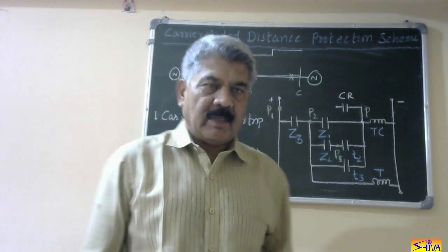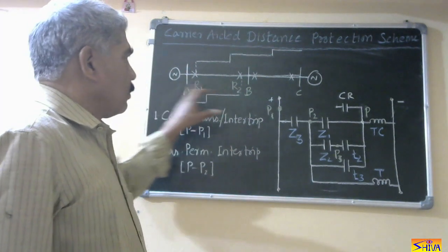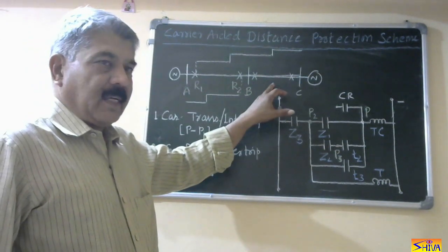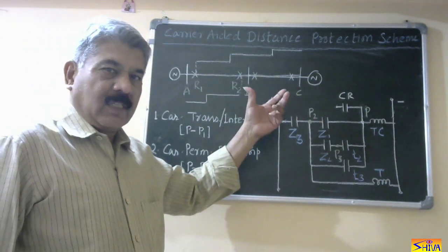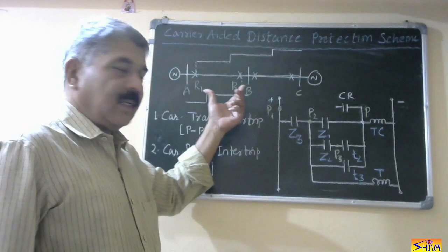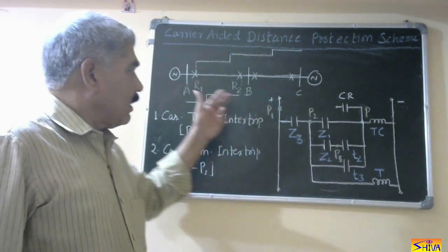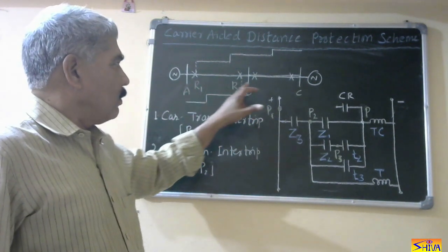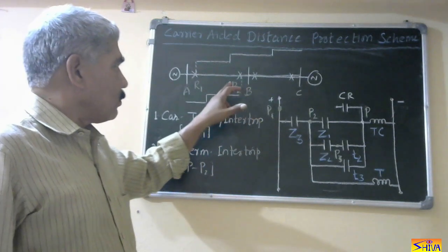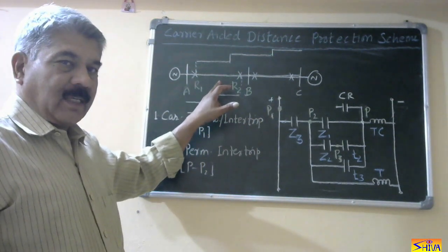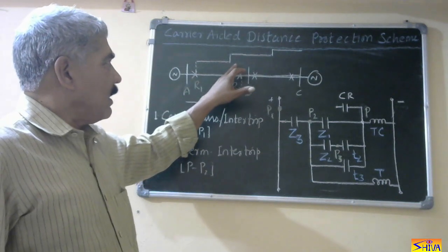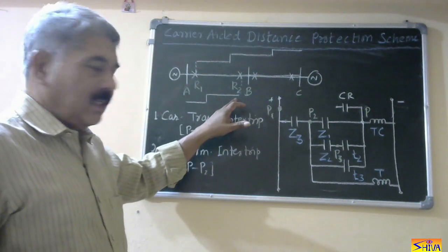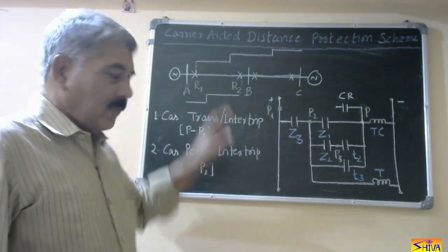Let us recall the principle. This is the simple system: two radial feeders with sources at both ends. As sources are at both ends, we require a relay at both ends of the line. We are providing three-step settings to the distance relays R1 and R2. For R1, it is 80% of the line in the first step, remaining 20% plus 30% of the next section in the second step, and so on. Similarly, we are providing settings to relay R2.